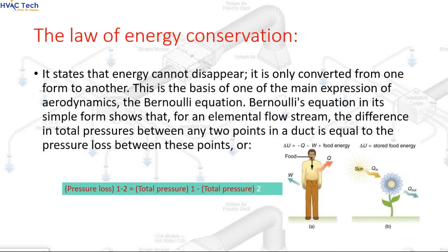The law of energy conservation states that energy cannot disappear; it is only converted from one form to another. This is the basis of one of the main expressions of aerodynamics: the Bernoulli equation. Bernoulli's equation in its simple form shows that, for an elemental flow stream, the difference in total pressures between any two points in a duct is equal to the pressure loss between these points: Pressure Loss (1 to 2) = Total Pressure 1 − Total Pressure 2.